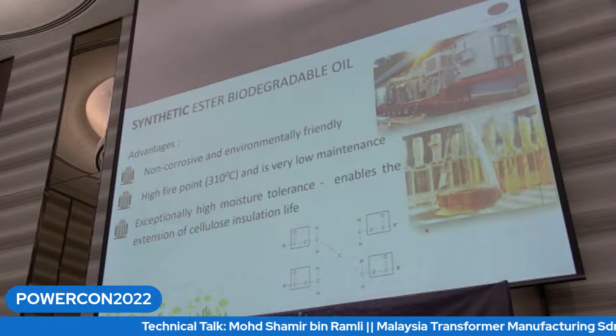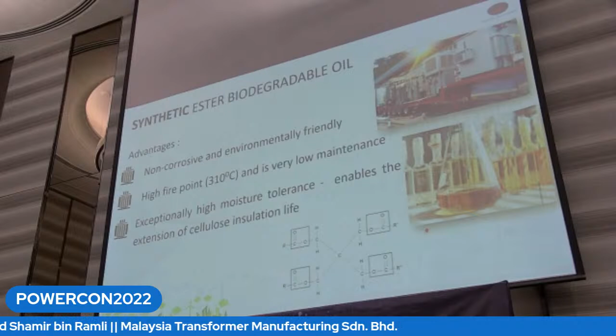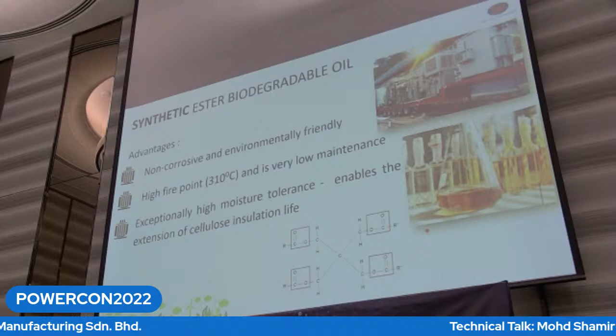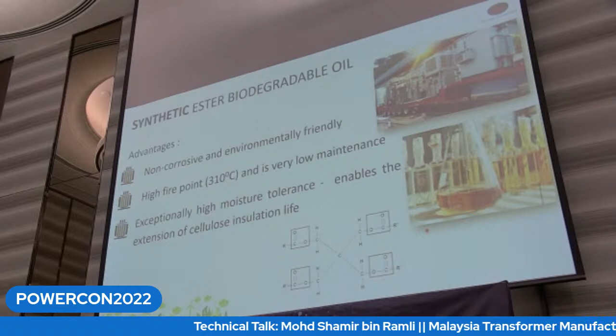We started two or three years back on synthetic ester biodegradable oil. These are the advantages of this type of oil, replacing the mineral oil: it is non-corrosive and also environmentally friendly. It has a higher fire point and is very low in maintenance. It additionally has a high moisture tolerance and enables the extension of cellulose insulation life.